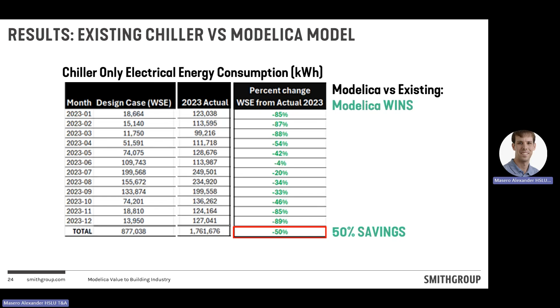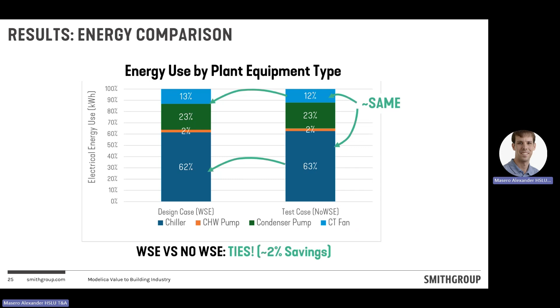If we compare the cases, the interesting thing is even though there's an advantage for the free cooling mode in the winter, based on that load profile with the cooling loads, there wasn't a ton of research-based process loads to keep the cooling constant and high throughout the year. So it ended up being kind of the same. Sometimes that's a takeaway too: if you have two options you can accurately model, and you get a comparable energy use solution at a lower investment cost, that's also something the client's interested in. I get the same performance for less money, so we're able to do that with more confidence.